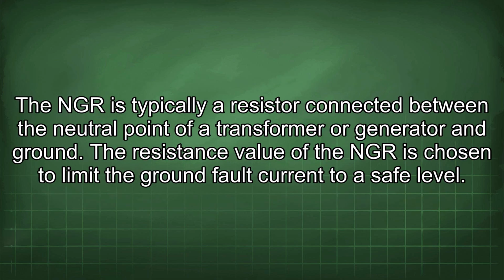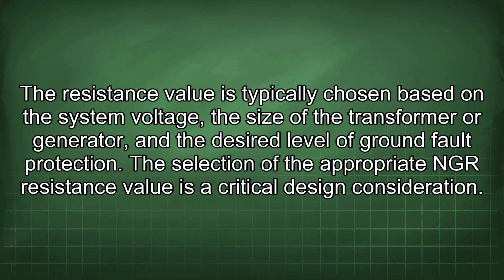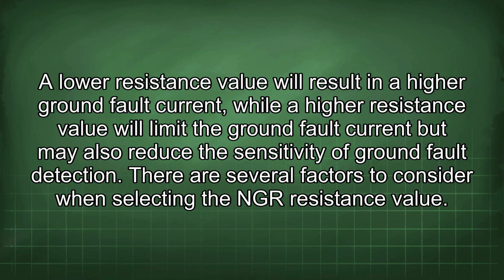The NGR is typically a resistor connected between the neutral point of a transformer or generator and ground. The resistance value of the NGR is chosen to limit the ground fault current to a safe level. The resistance value is typically chosen based on the system voltage, the size of the transformer or generator, and the desired level of ground fault protection. The selection of the appropriate NGR resistance value is a critical design consideration. A lower resistance value will result in a higher ground fault current, while a higher resistance value will limit the ground fault current but may also reduce the sensitivity of ground fault detection.